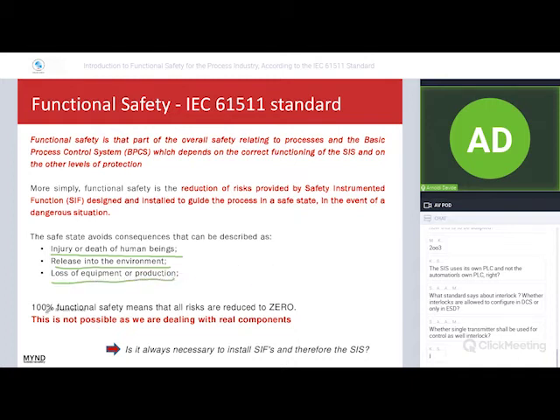Be careful, because we cannot speak about 100% functional safety, because this means reducing the risk to zero. And this is not possible, since the devices installed in the safety instrumented system are real, and real instruments can fail. The question is: is it always necessary to install SIFs and therefore a safety instrumented system?